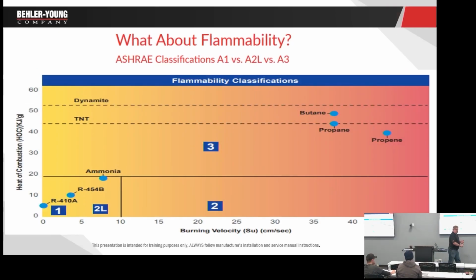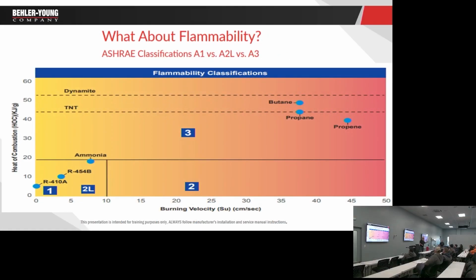It takes a flame to ignite it. A spark won't ignite it. We need a large quantity of it. So what do I mean? We all have taken a combustion class. We talked about lower flammability limits, or lower explosive limits. Propane has a LFL, lower flammability limit, of 2%. So I'd need to fill this room with at least 2% propane to make it ignite, right? Anything less, it's not going to ignite. Natural gas is about 5%. If you figured out the square footage of this room, I'd need a lot of propane to get this room to 2% to where it would ignite. This stuff is about 12%.